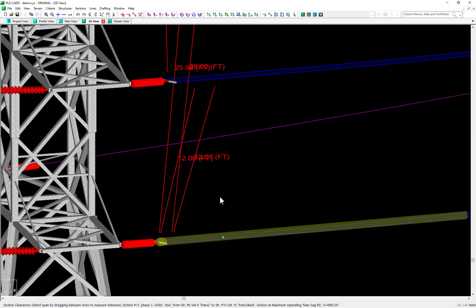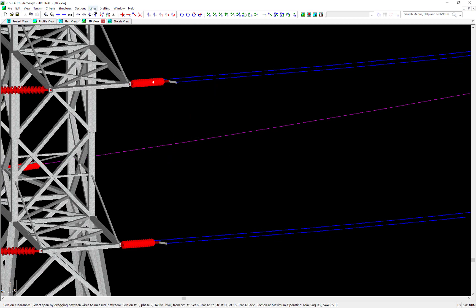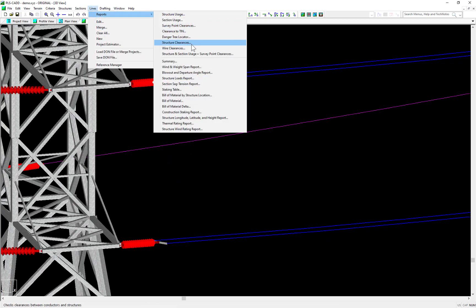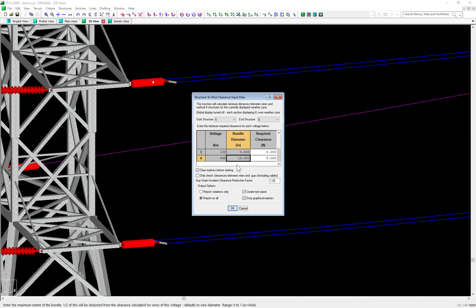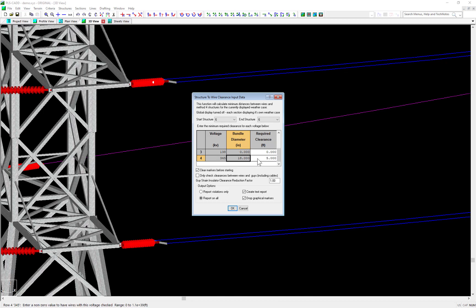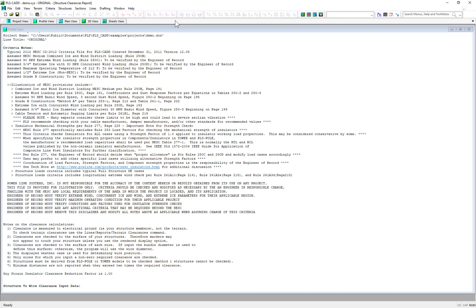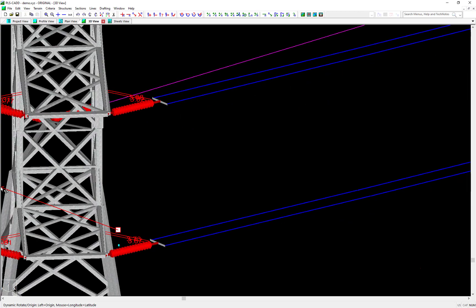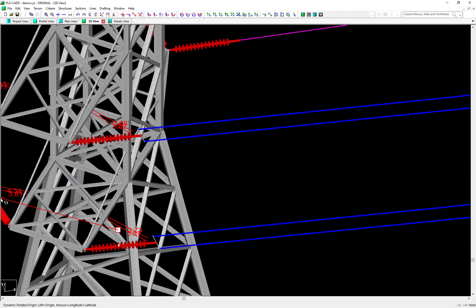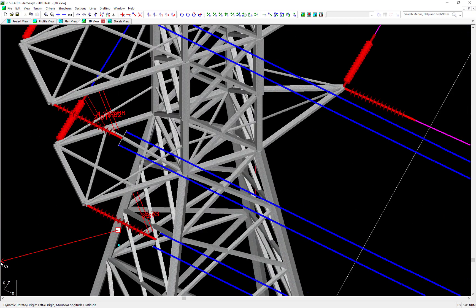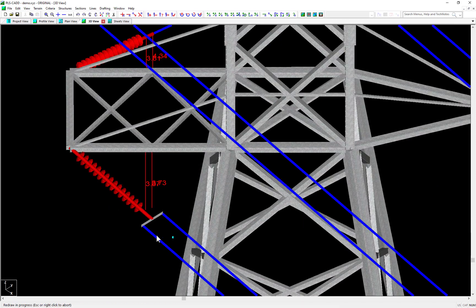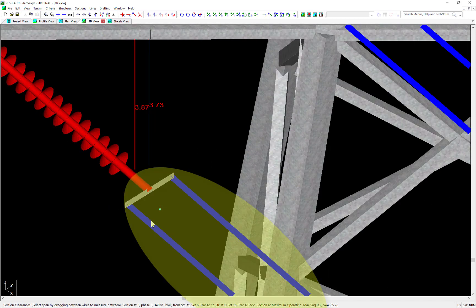And I'll also run an example now showing how you can account for the bundle geometry using structure clearance functions as well. Notice how when I run this report, it automatically pulls in the bundle spacing of 1.5 feet I entered into the section. And when I enter in 5 feet of required clearance and run the report for just structure 6, you'll see two markers drawn at the beginning of the span to the nearest structure component. The 3.87 feet is measuring the energized zone of the insulator and the 3.73 feet is measuring to the 1.5 foot diameter conductor bundle.